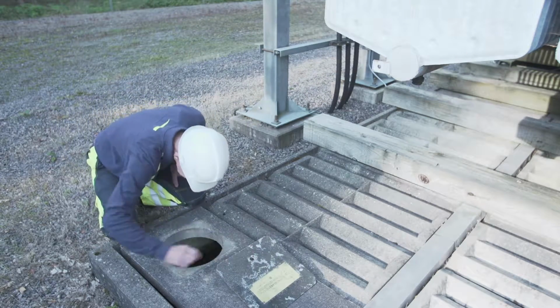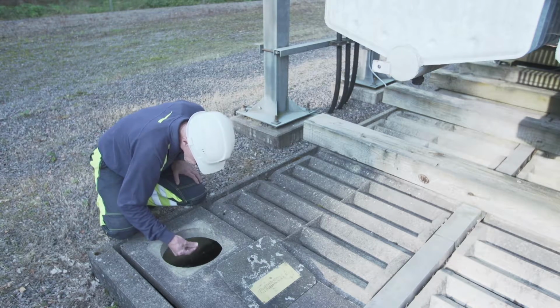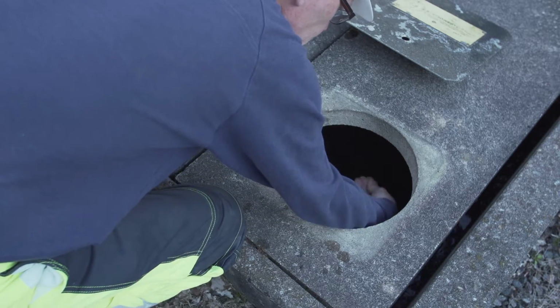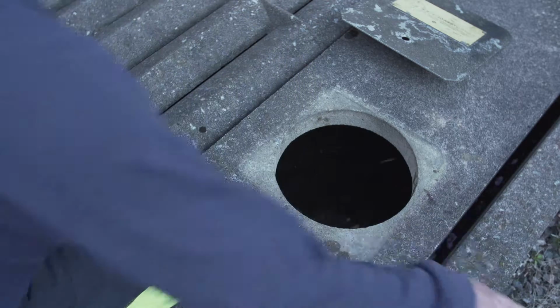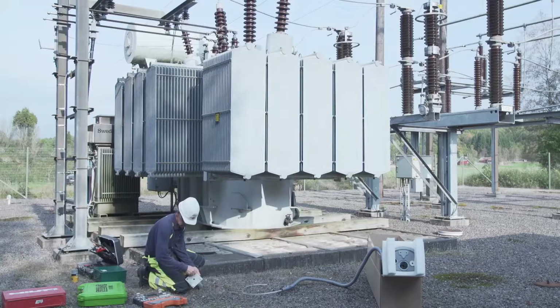Check and classify the pit status. If the pit is in poor condition, cancel the installation, comment on the installation protocol, and notify the customer. Never install and commission a unit where cleaning is necessary.